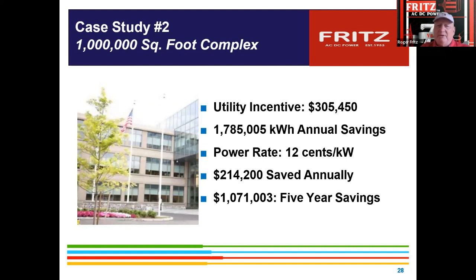This happened to be about a 1 million square foot facility. When they first walked in, they said, "Oh, we've got drives on." Yeah, they did, everything above 30 horsepower. About 100 motors later, found in the facility, incentives of about $305,000, and a couple hundred thousand dollars of annual savings. So it's definitely good. Heidi came up with a concept about being a motor hunter.